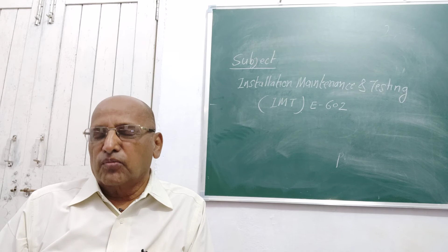So in a pole mounted substation, what is the first requirement? The first requirement is the erection of two poles, which are either PCC poles in rural areas, or in urban or city areas you use a rail pole or RSJ. After erection of the poles, you have to install the horizontal double C channels for the installation of the transformer on the structure. When this is done, then 50% of the work is over. After that, for the other required equipment, on the upper side we require the lightning arrestor, DO fuse and AB switch, and below the transformer we have to use the LT distribution box.